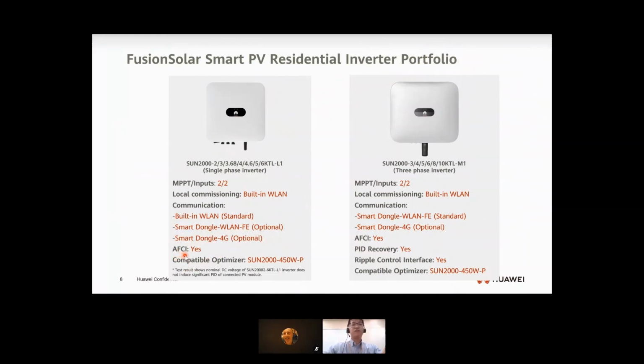AFCI function is an arc fault circuit interrupter. It's a safety feature that deals with DC arcing. We know that in residential or C&I scenarios, if there are some bad connections between the PV module connectors, DC arcing may occur, and that's one of the main reasons causing fire hazard. So with the AFCI function as standard, we can overcome the risk of DC arcing by shutting down this inverter very quickly, in 0.5 seconds, so instantly shut down, and it's very safe for the homeowner. This is one of the important features that Huawei is pushing in the market.